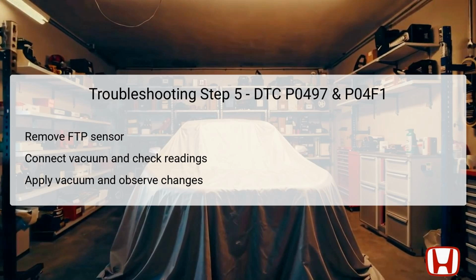Now, slowly apply about 1.3 kilopascals or 0.4 inches of vacuum to the sensor. Check the reading on the HDS again; a change in the value signals that the sensor is functioning correctly. However, if there's no change in reading, this indicates a fault. Replacement of the FTP sensor will be necessary to resolve the issue.